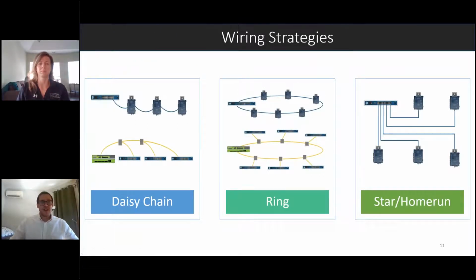Now we're going to move into wiring strategies, which I think is a good, important discussion. We'll start with the daisy chain on the left. The daisy chain is technically the same wiring strategy used for MSTP LAN and Modbus RTU — they use serial communications and a daisy chain. What's really good about a daisy chain is it cuts back on the amount of wiring used, so your wiring costs go down, as opposed to a star home run where everything is wired back to a central point. A daisy chain, as you can see here, uses a lot less wiring, which can help with your costs.